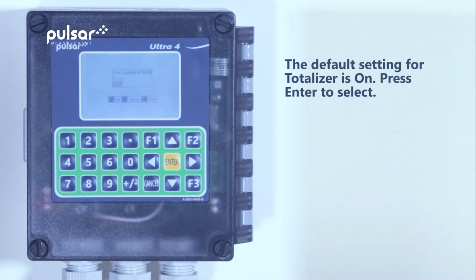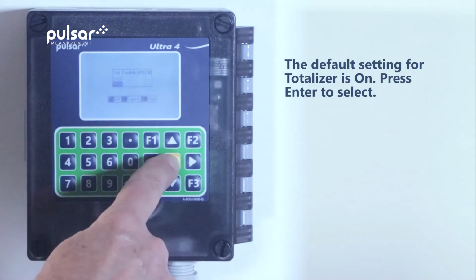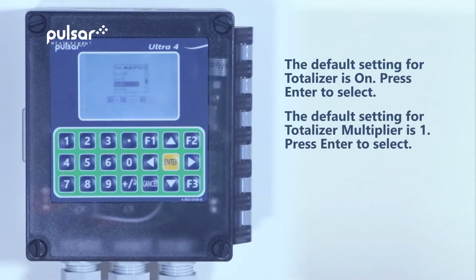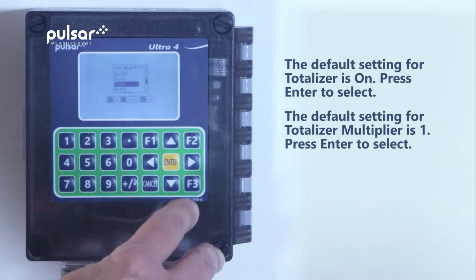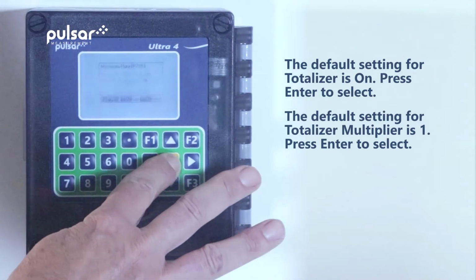It's time to set up the totalizer. In most cases, we'll want the totalizer on. It's also the default setting, so we simply hit enter. The totalizer multiplier sets the factor by which the calculated volume will be divided or multiplied before being displayed. In this case, we'll multiply by a factor of 1 by hitting enter.